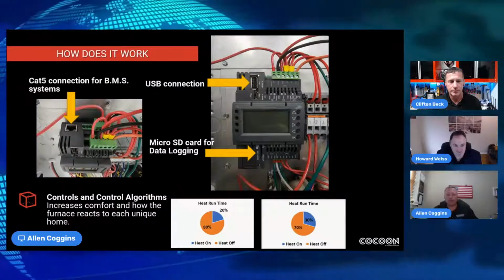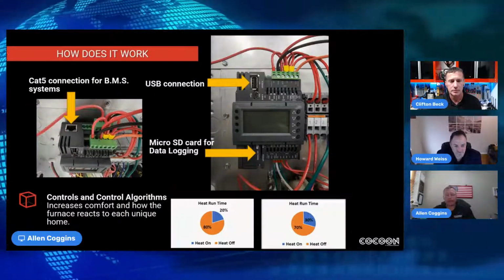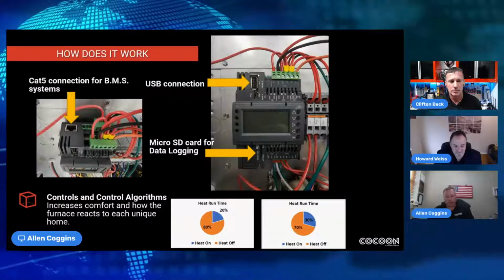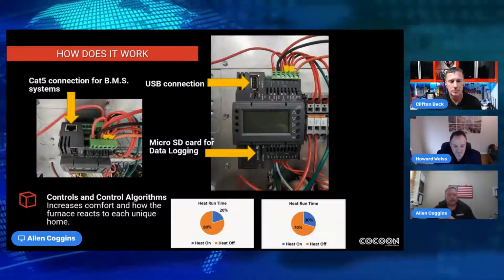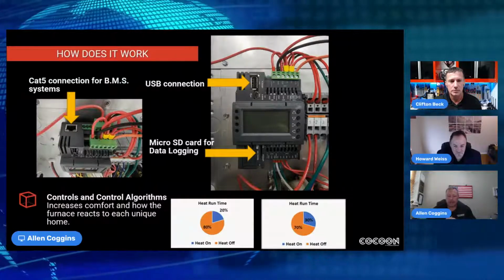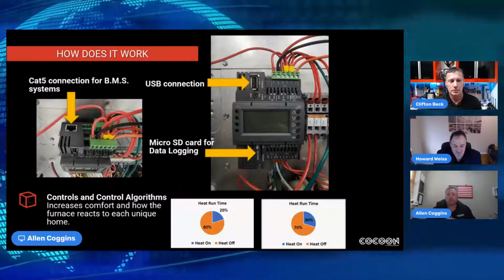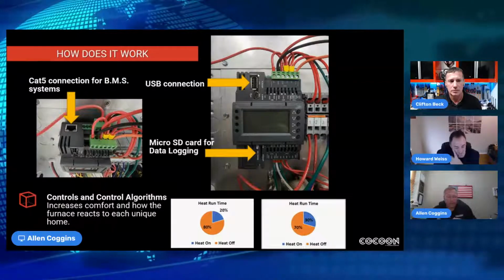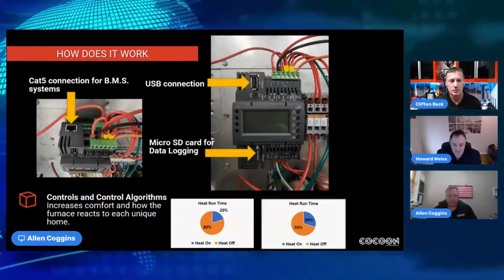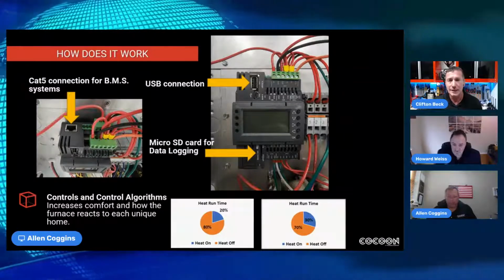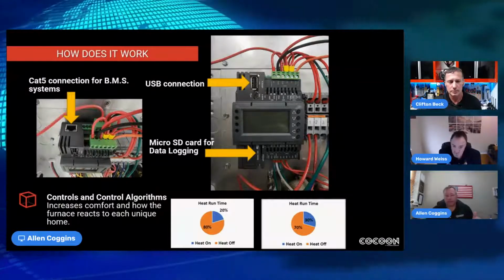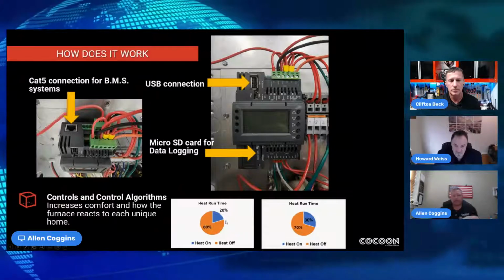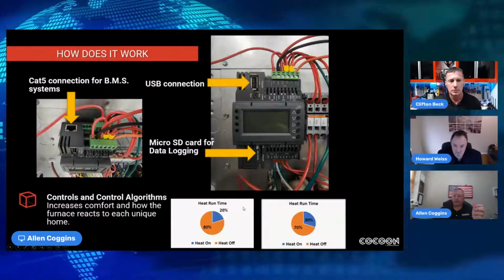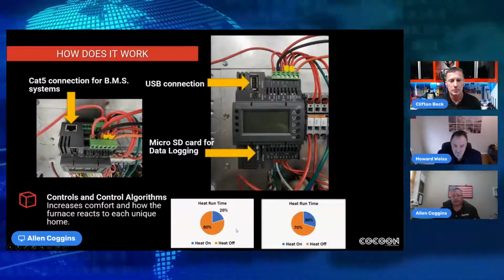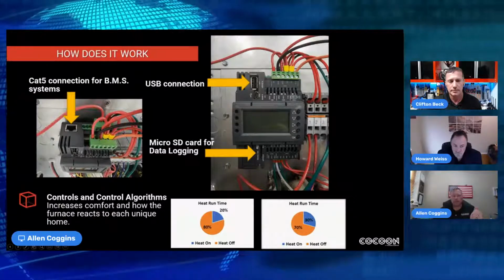With this, once we start capturing the data — and we do data log with this — we can then start to customize how the furnace runs to that home. Of course, you're not going to want to make a change like that until you've got at least a good year, maybe two years' worth of data to establish a baseline. What we're seeing is that we can capture the runtime, basically the duty cycles, when you get right down to it.